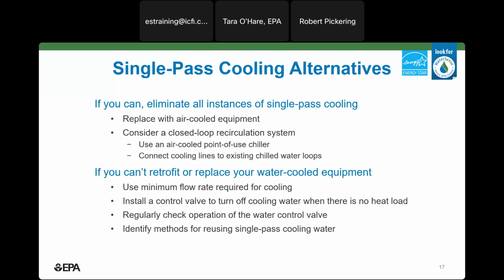In cases where you can't eliminate single pass water use, make sure that your system is using the absolute minimum volume needed. Check the equipment specifications and make sure that you're getting the temperature rise in the water that you're applying. Also make sure that the water turns off when the motor or the compressor isn't running. This is often controlled by a solenoid valve so that it shuts the valve when the motor or the compressor is no longer running. But in some cases, this valve can fail and it allows the water to flow at all times. So this is a maintenance item that's worth checking up on and that often needs attention. In some cases, single pass cooling water can be collected and reused for another purpose, but it really is just best to eliminate it before its use.